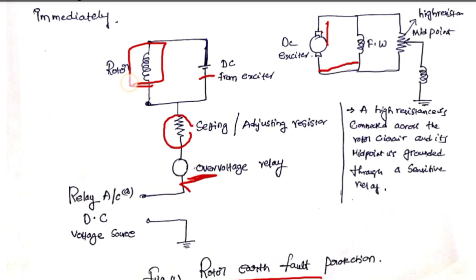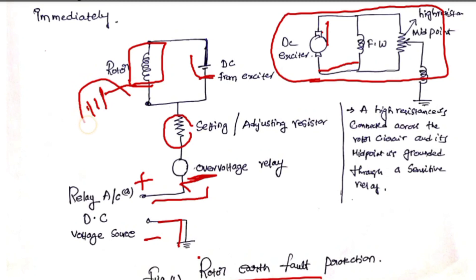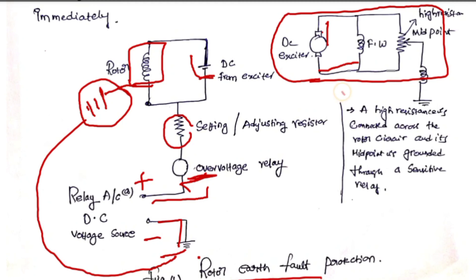This is the rotor field winding, and we connected an exciter. This is the equivalent circuit of the DC exciter and field winding in case of an alternator. When the rotor gets earthed for the first time in large alternators, AC or DC voltage is impressed between the rotor field winding and ground. This is the rotor earth fault protection — large alternators can be protected from various types of rotor earth faults in this way.